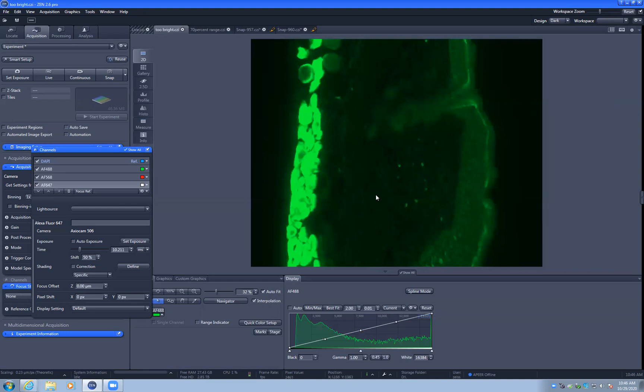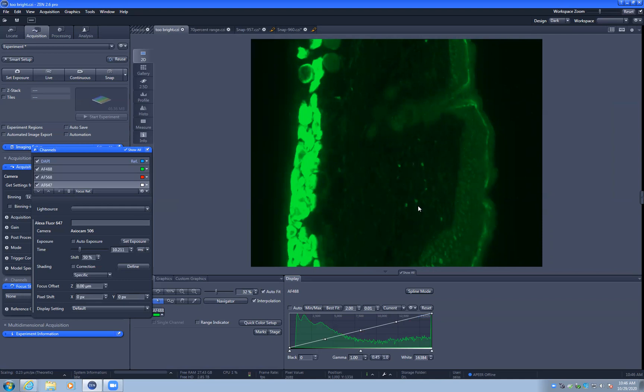However, this region here looks good. But there really is no reason to have to saturate the left in order to see what's going on on the right. Because in fact, the camera only needs a thousand or two counts, intensity counts, in order to get a really nice clean image. So even with the brightest areas not saturated, there is good signal there.